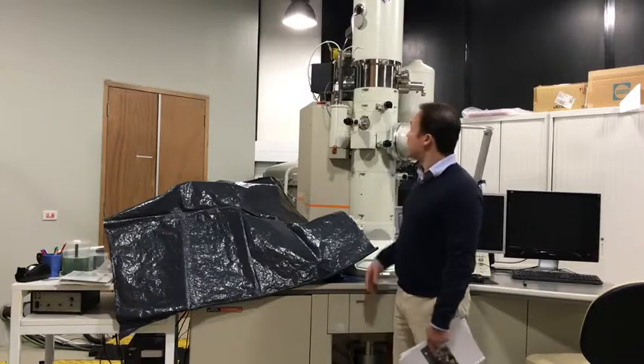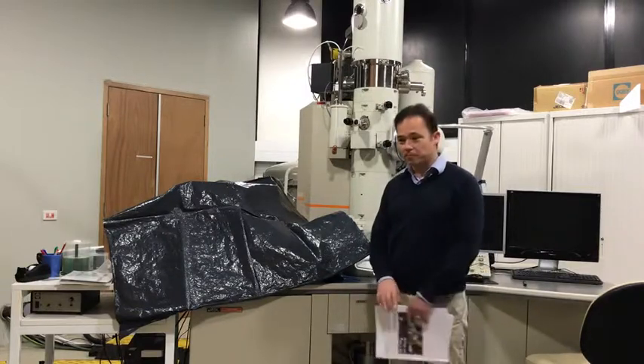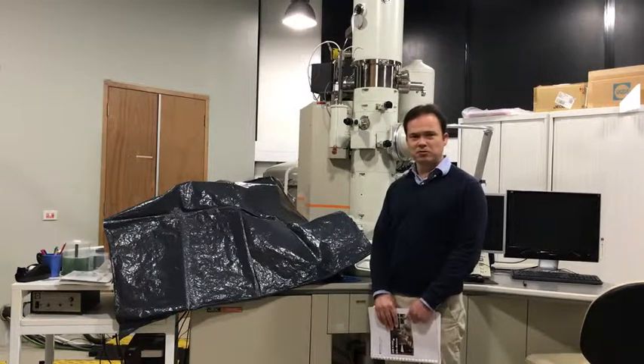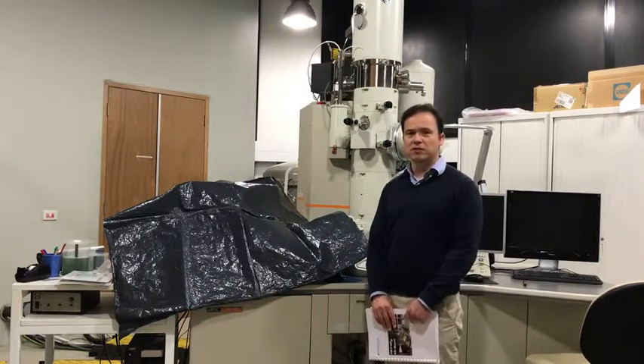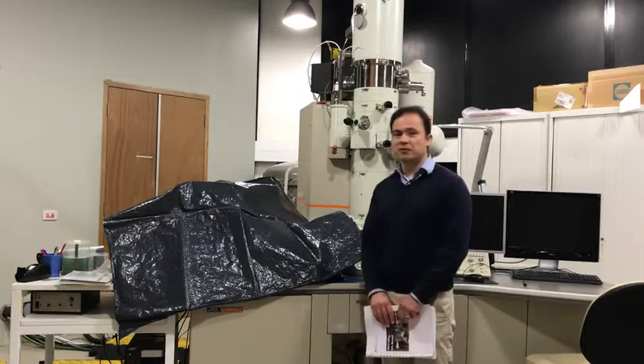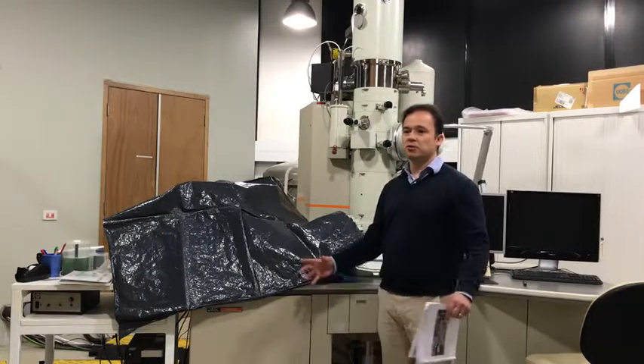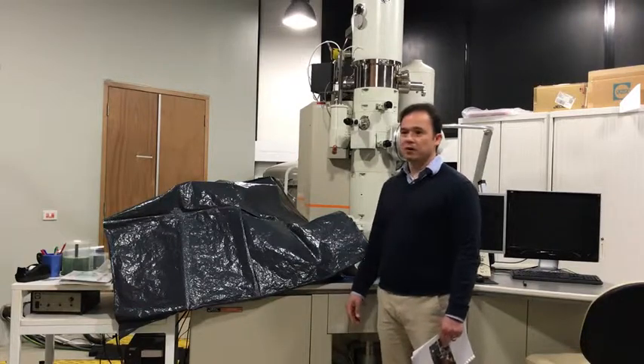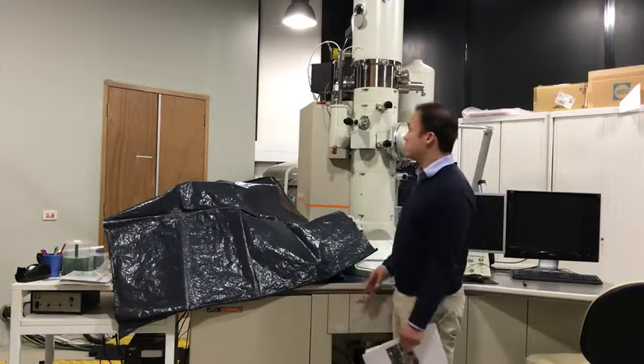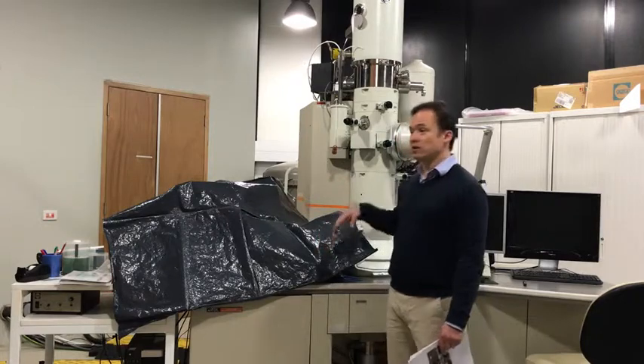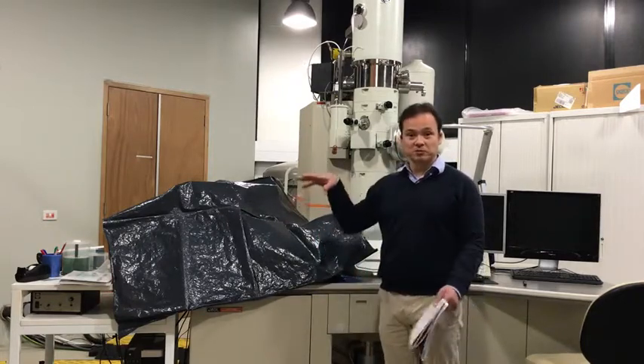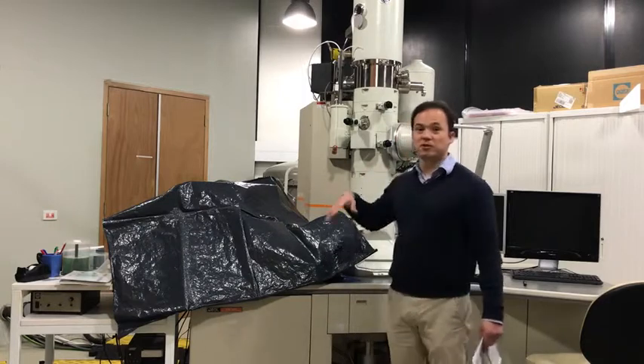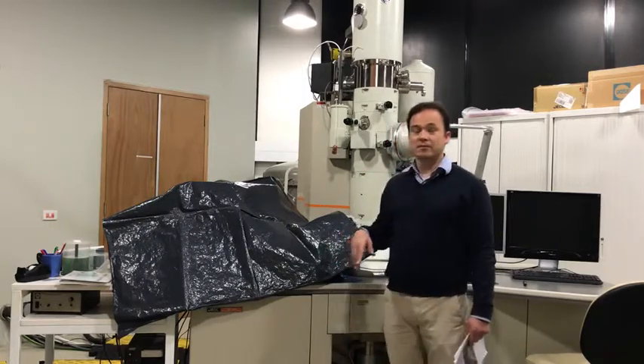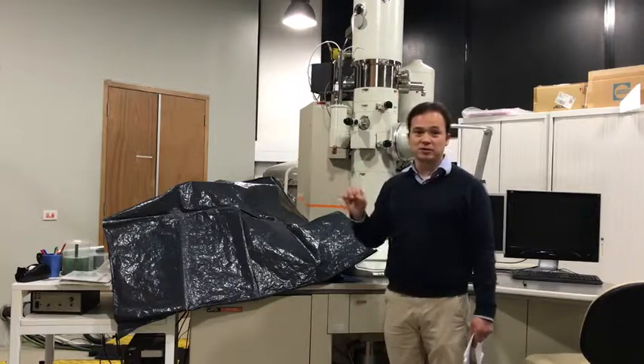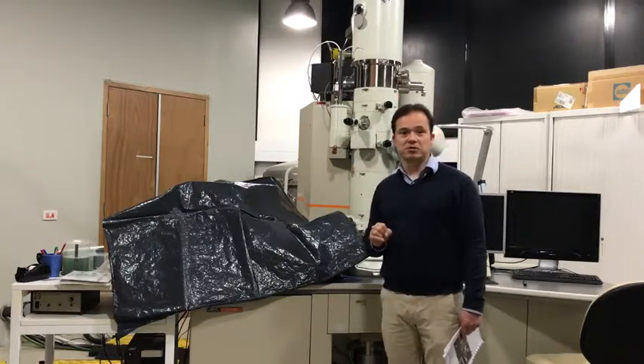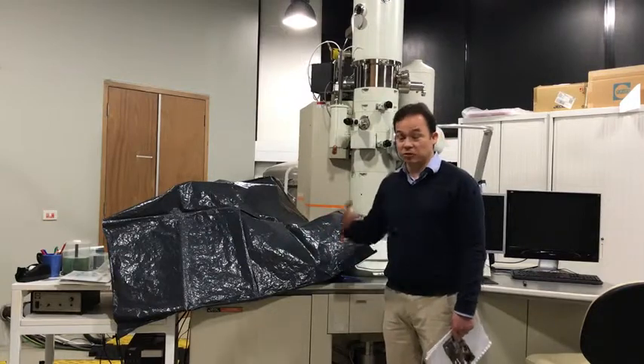We recently had a new gun put on this microscope. Guns are usually worth around $300,000 to $350,000, and they're flown from the factory in Japan in shockproof crates, all under vacuum. So the gun is continuously under vacuum while it's in transit, and while it's being fitted onto the microscope. And so the tip in there, which is almost atomically sharp, is never exposed to atmosphere, which would destroy it essentially.